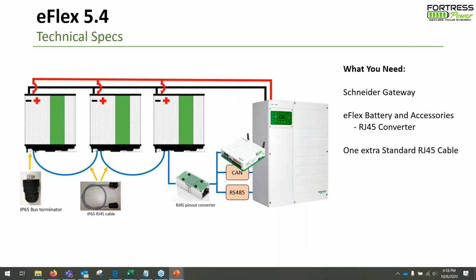Basically, the way it works is your batteries are the same, they're connected to a bus bar, but the main difference is, in case we haven't explained it yet, the batteries communicate state of charge information directly to the inverter, directly to the gateway. So you're going to need this Schneider gateway that connects to your inverter. And this has many advantages, right? The battery is constantly communicating to the gateway, which is communicating via Xanbus with the Schneider inverter. This will improve efficiency, but not only that, it will make sure that the inverter turns off if the batteries are in any danger. The battery can tell the inverter, this is working, this is not working. It's much more accurate. Everything that you need to connect to the Schneider is included in the Eflex box: the pinout converter, the cable, the terminator. The only thing that's not included is the Schneider gateway, which is another accessory you have to get.